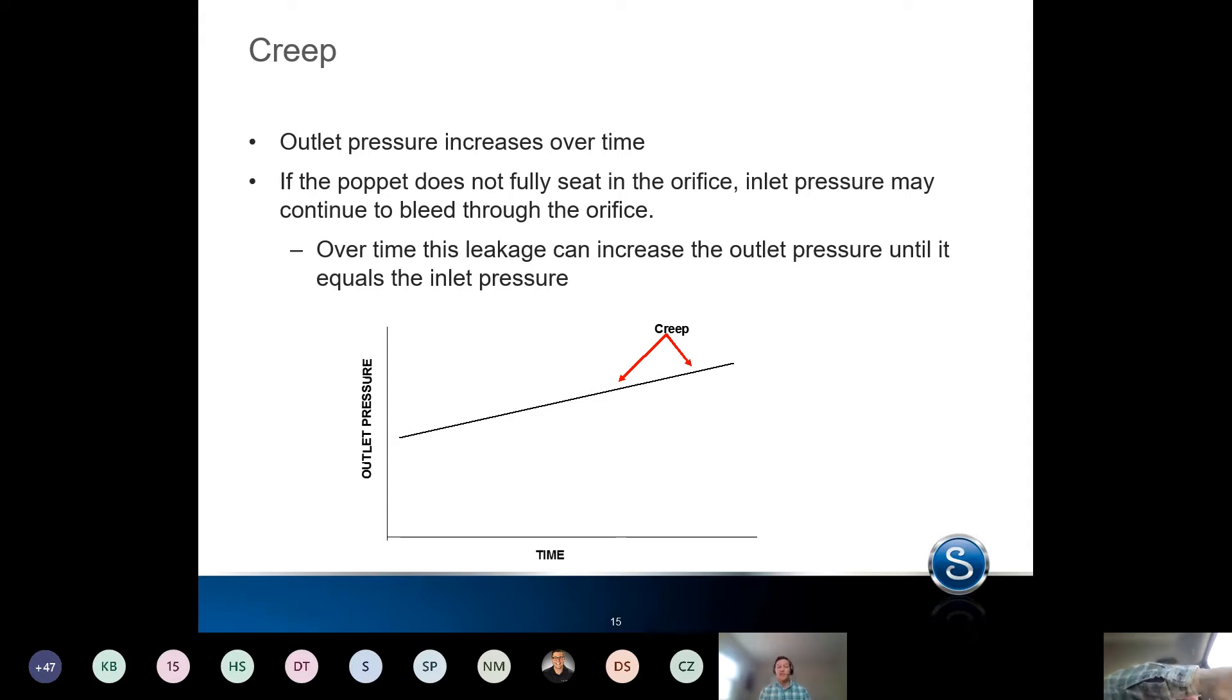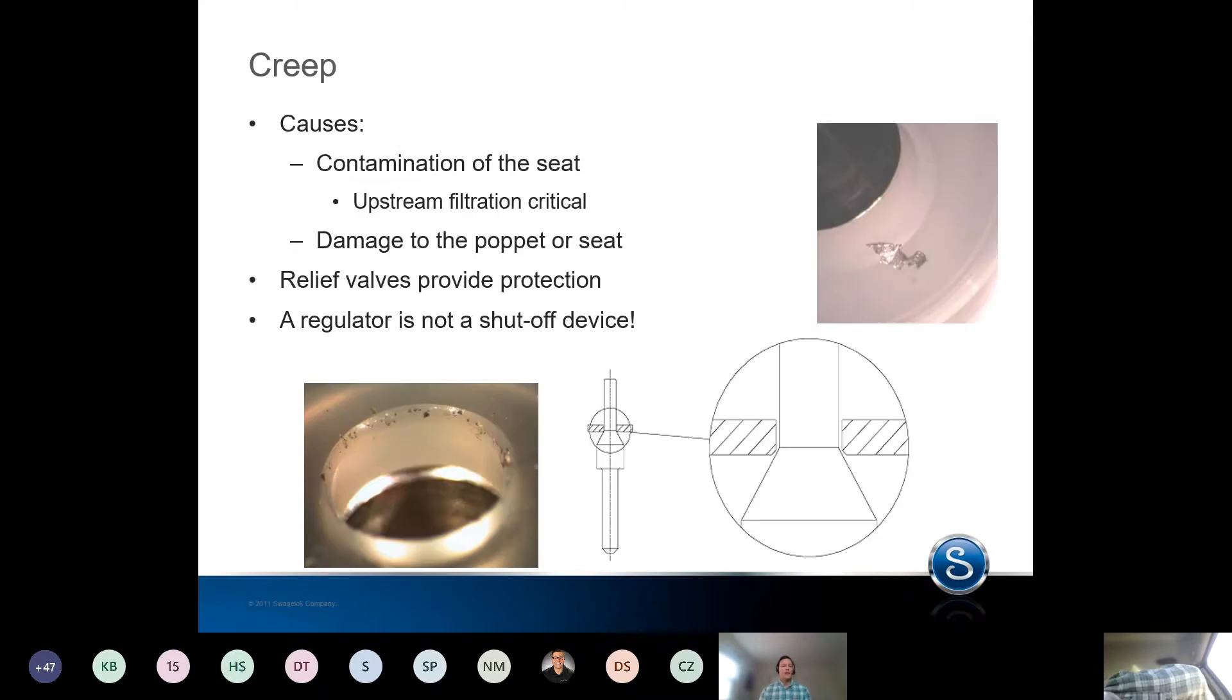So essentially a seat leak, right? And creep is typically caused by some sort of debris or damage on the seat.